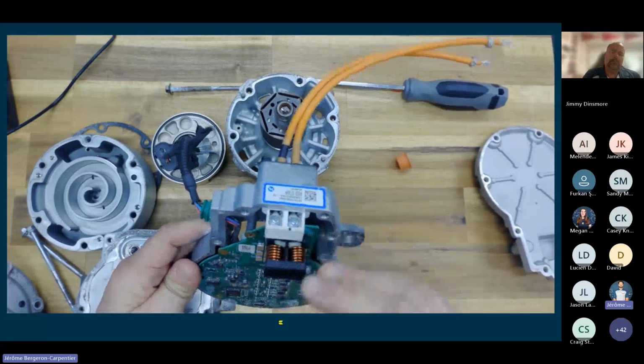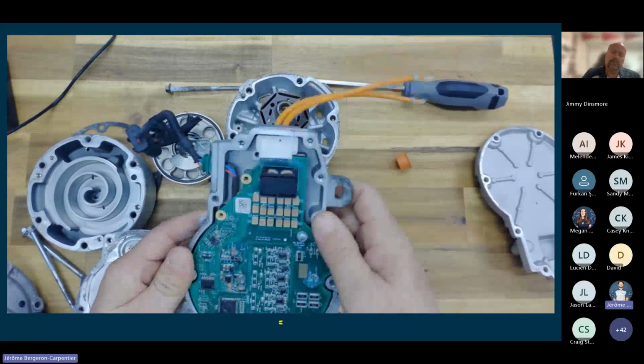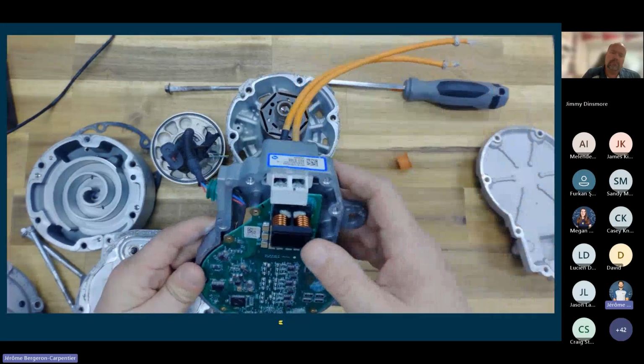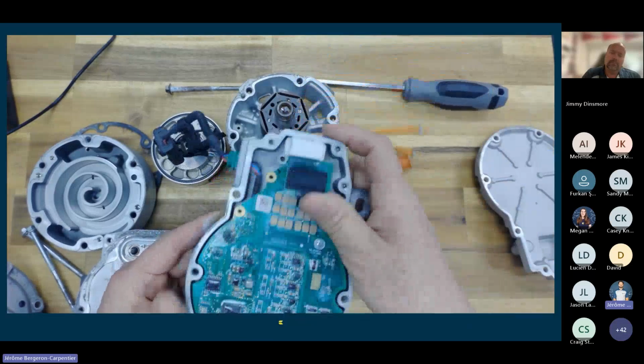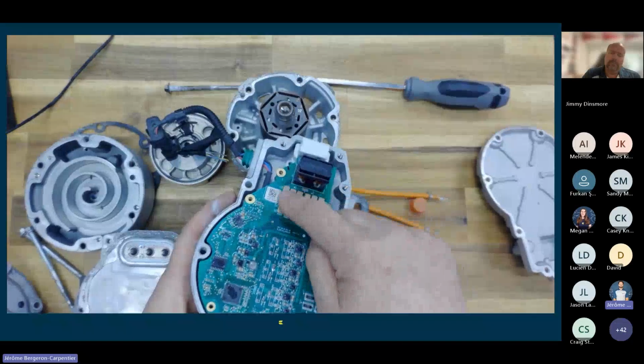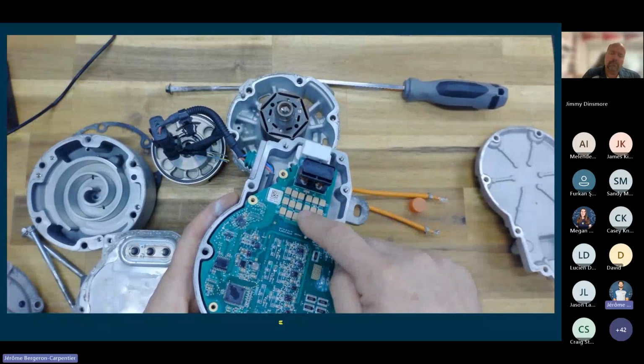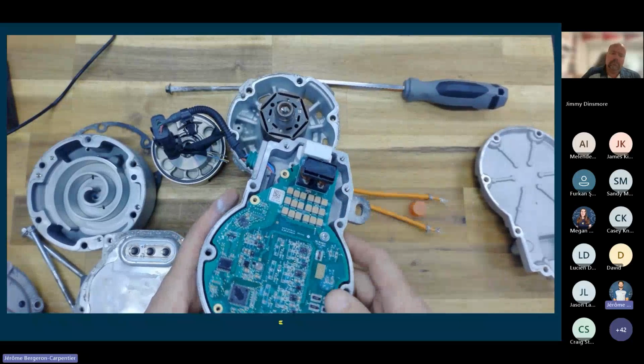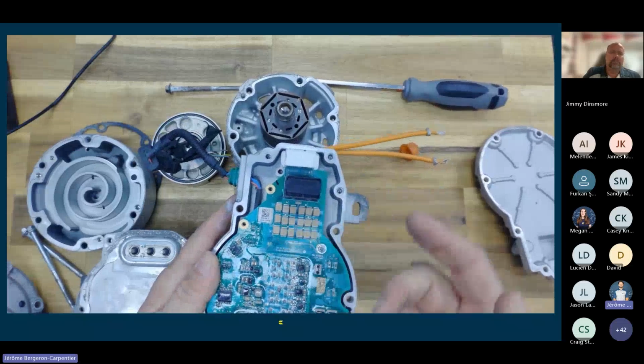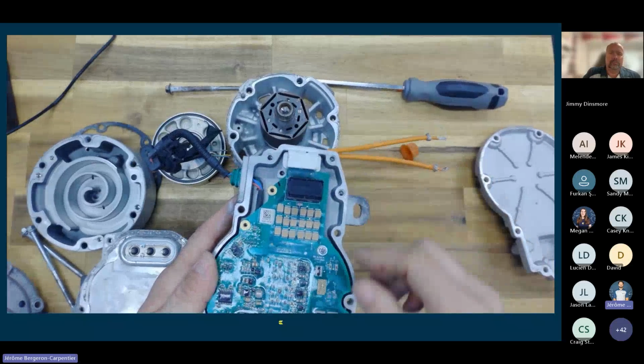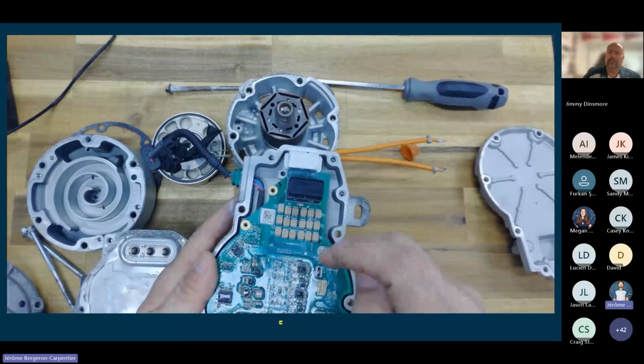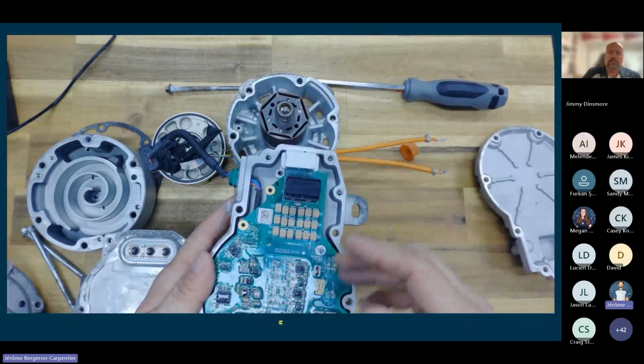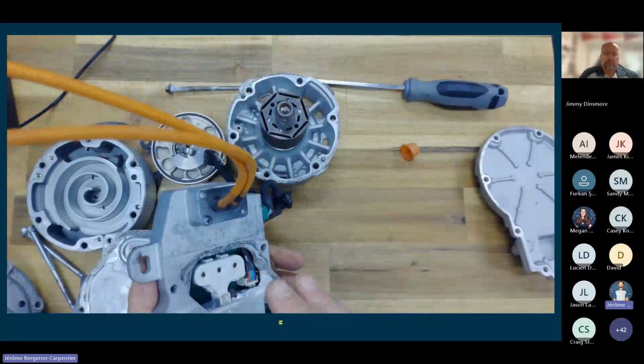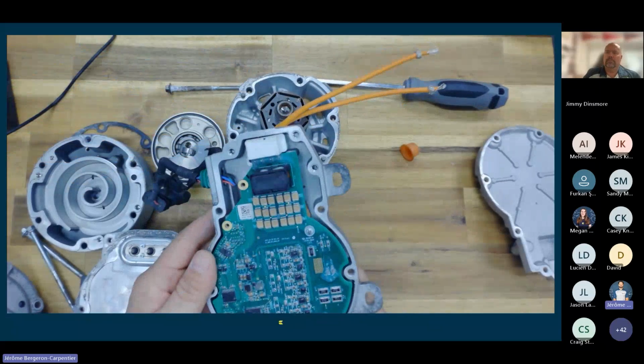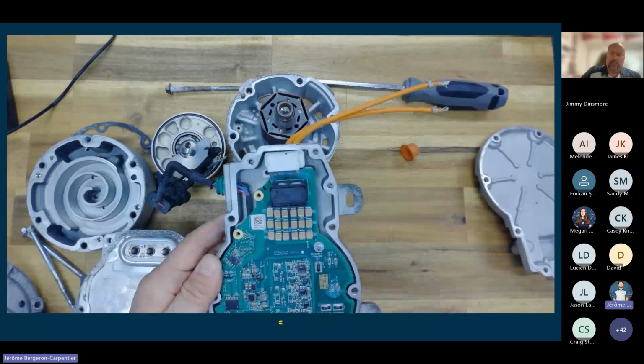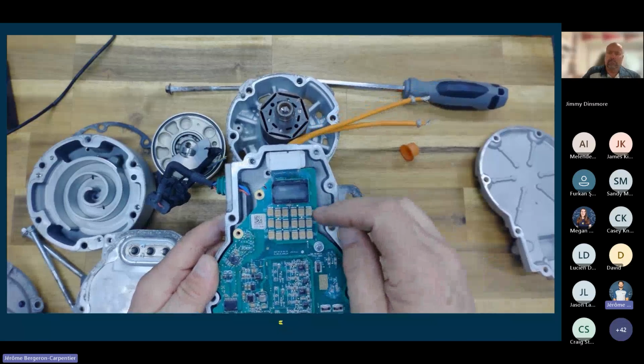Basically these two guys will take away the DC current ripple that would be present on the DC voltage, not AC voltage. And then we can see all the IGBTs. Now, if you remember, we had 27 segments, so essentially there's nine groupings for the three-phase. So we have 1, 2, 3, 4, 5, 6, which will pair up to excite our stator to turn the rotor inside here. So once again, it's a very unique setup, but there's 3 for each phase.